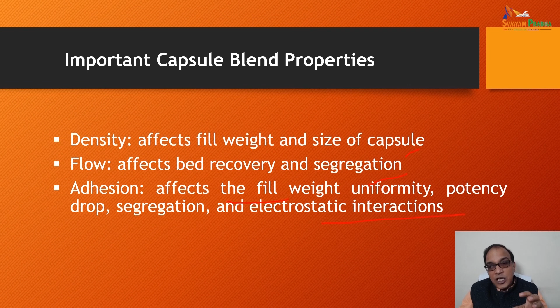Adhesion affects the fill weight uniformity, potency drop, segregation and electrostatic interactions. Water content affects the wettability, dissolution and shell and content stability, while the compactability affects the fill weight uniformity, plug formation, tamp compression pressure, plug retention in dosing tubes and dosing discs, and dissolution. While the compressibility affects the fill weight, tamp compression pressure and capsule size selection. So these are the important capsule blend properties.